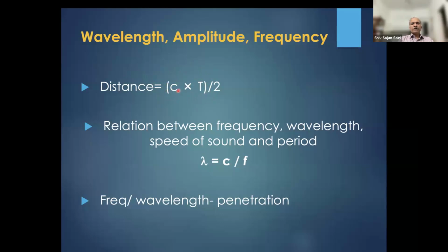C is the speed of sound. When I say sound, I mean ultrasound. So C is the speed of the ultrasound, which is 1540 meters per second. T is the time. The machine knows what time it takes, and you apply C into T divided by 2. Then this is the distance from the probe to the anatomical organ of interest.